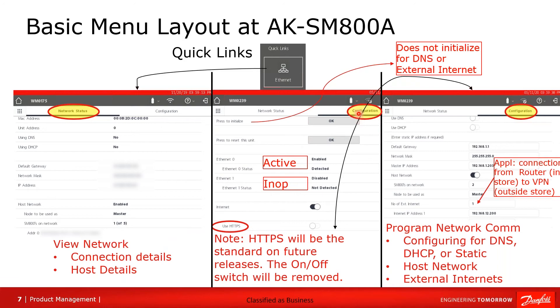For further configuration, press the Configuration option. Something new to the control is the Press to Initialize button. If you make changes to your network connections, go to Initialize to activate those changes — previously you had to reset the control, but no longer. If your host network didn't come up or you're not successful getting online, always go to Configuration and press Initialize. There is also a reset option if you choose. Regarding the two Ethernet ports, Ethernet zero is the only active one. Ethernet one is for future use, so it's inoperable — keep it disabled.